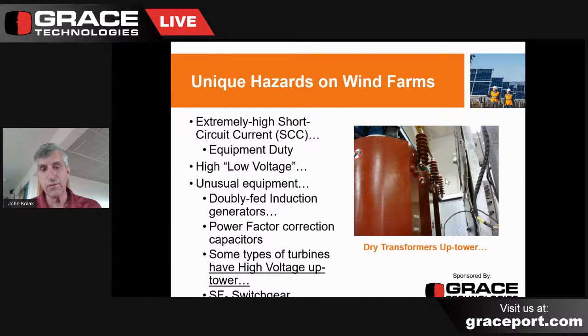They will tell you what the generator will output in a fault. Definitely use that data if you can, rather than using calculated values, because they have a better insight into that than we would just calculating it. There are also power factor correction capacitors, which have a bad history of exploding from time to time, more of a safety training aspect, but there's a unique piece of equipment for which they need particular training.